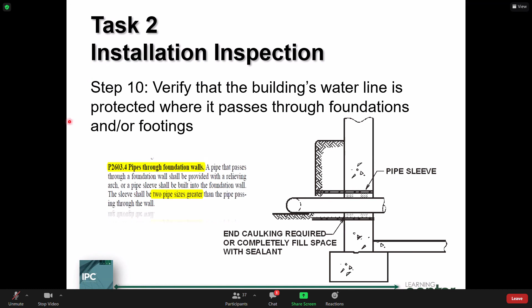Because if this is 1-inch pipe, the next pipe size over 1 inch is 1.25 inches, and then 1.5 inches, right? 1.25 inches, then 1.5 inches. So minimum 1.5 inches, okay? And given the code section, that's exactly what we're talking about.